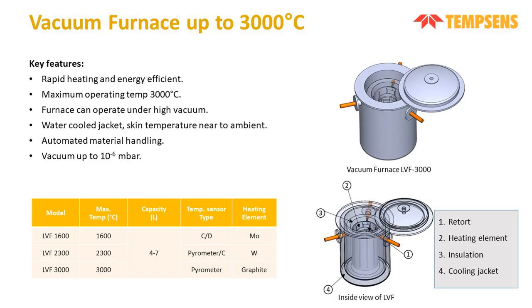Our standard vacuum furnace has around 4 to 7 liters of capacity. For the thermocouple sensors, in contact type we have C type thermocouples, and in non-contact type we have pyrometers. Accordingly, we select the heating element according to the temperature and the environment in the furnace. For 1600 we have gone for molybdenum, for 2300 we have gone for tungsten, and at 3000 degrees Celsius we go for graphite type heaters.